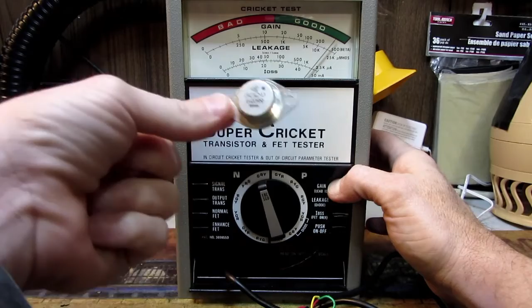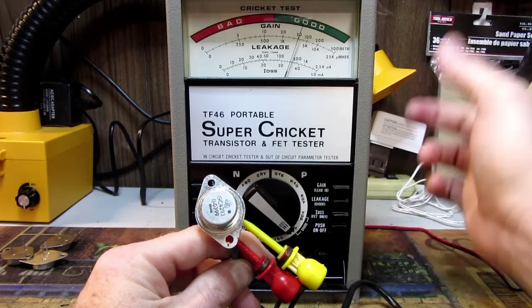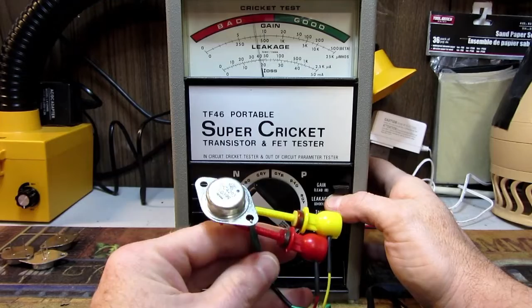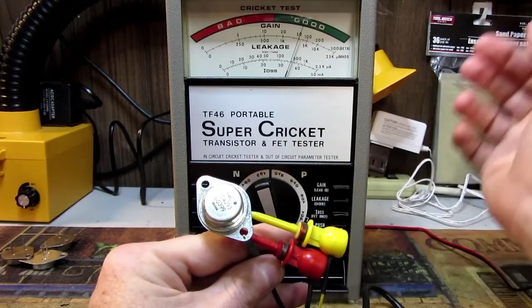Okay, we have the germanium transistor connected to the Super Cricket, and so now we're going to go through the process again. We're starting at position 1 here. Okay, bingo, we have a reading. So the very first thing you're going to do is hit leakage, and you're going to read that scale right there. So according to this, it's got about 40 microamps of leakage in this position. Now we're going to go to the next position, and there again we're getting the second reading, which is correct. So now we'll hit the leakage again, and on this position we have a little above 50 microamps, probably around 55 microamps of leakage.